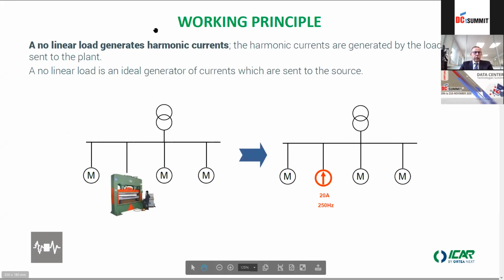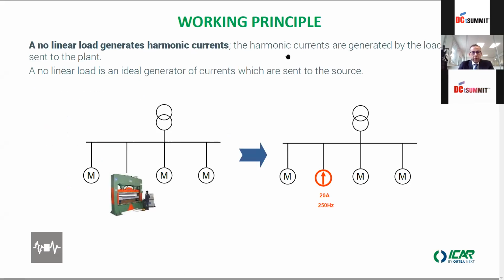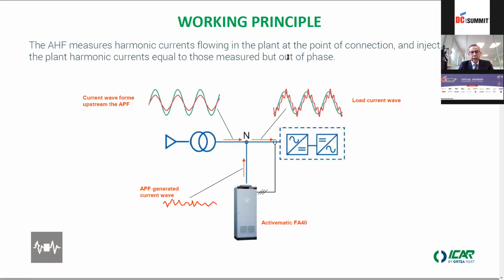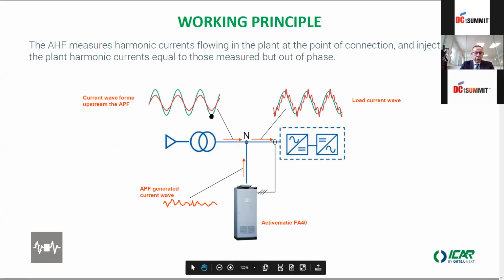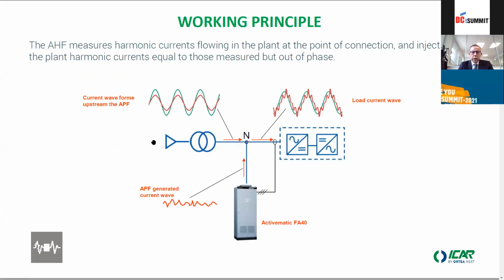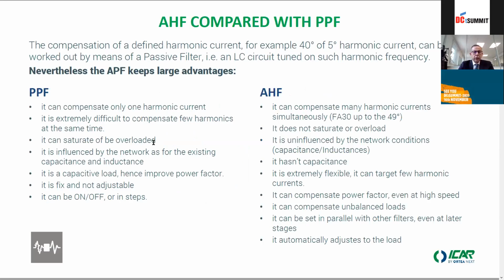So the working principle of the harmonic currents is very easy. I think all of you should know how it influences the line. It creates a lot of troubles to the line that can be thrown back to the source. So having an active filter will kill these harmonics and give the load, and vice versa against the main feeding line, so from the public distribution line, do not throw back harmonics to the line. So this will improve the energy quality.